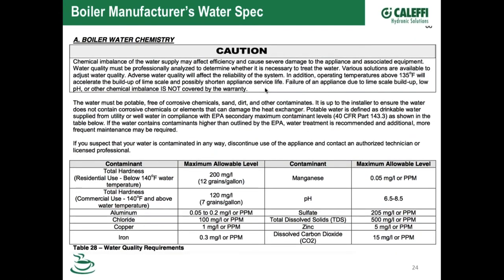What we did is go to some of the different boiler manufacturers' websites and pull off their water spec information. Here's an example - they tell you the hardness needs to be below a certain level. The English unit we typically use is grains per gallon when talking about hardness, but you can convert that into parts per million, or the metric unit would be milligrams per liter.